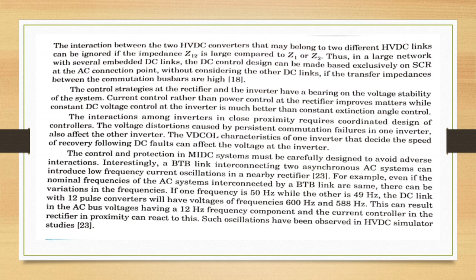Interactions among inverters in close proximity require coordinated design of controllers. Voltage distortions caused by persistent commutation failures in one inverter also will affect the other inverter. VDCOL characteristics of one inverter that decide the speed of recovery following DC faults can affect the voltage at the inverter. Control and protection in MTDC systems must be carefully designed to avoid adverse interactions.